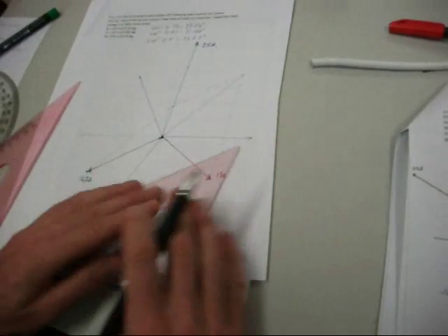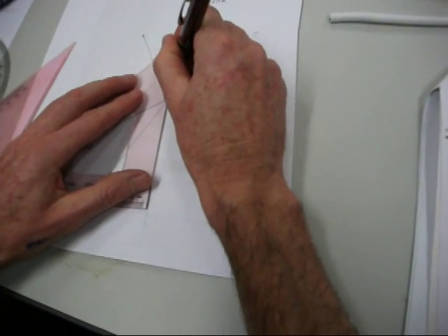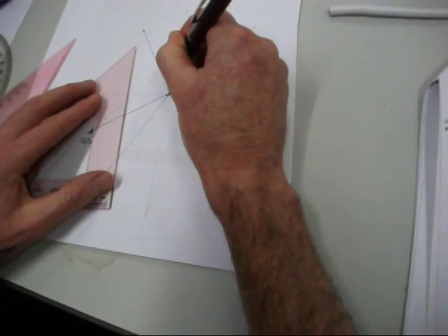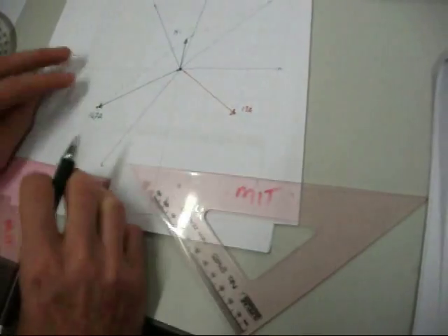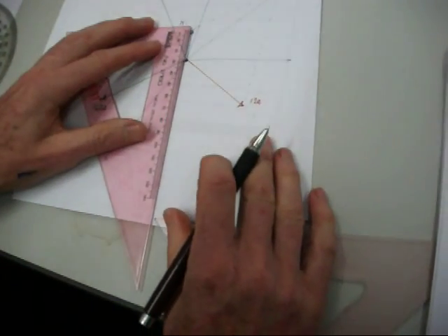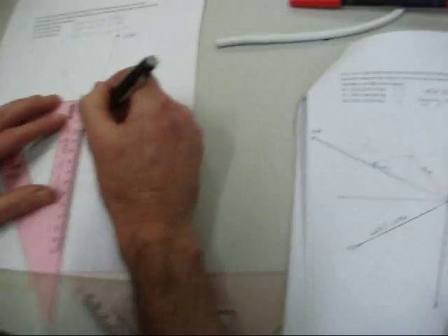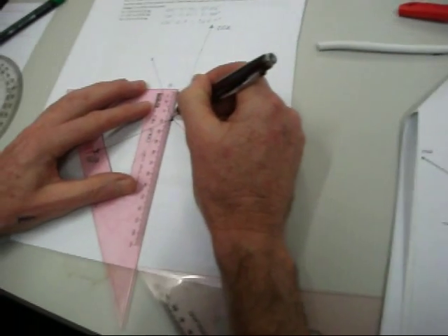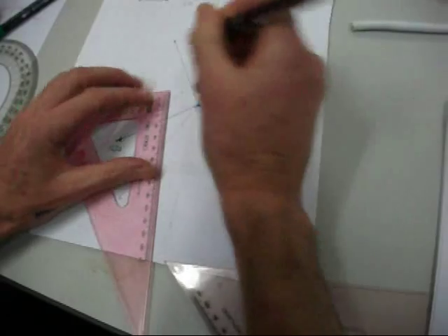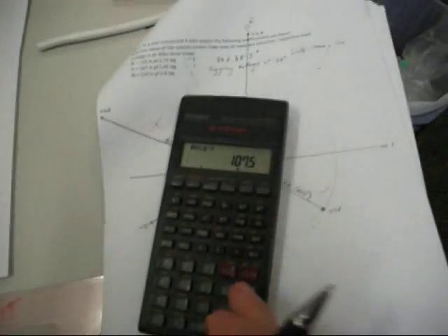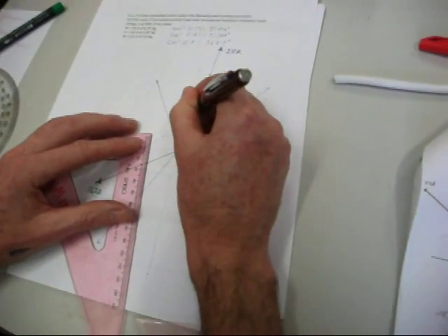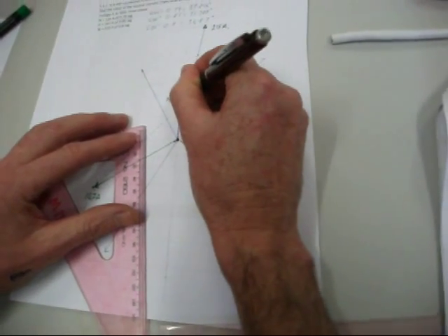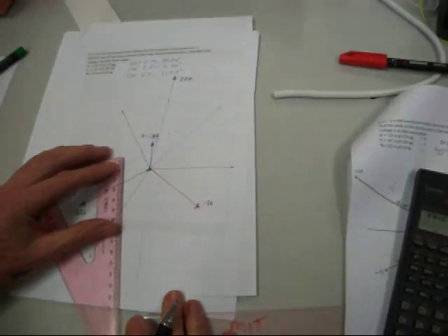Where the two meet is a neutral current. It measures 25, 26, 27, 28, 29. 29 times 2 because we're using a half scale, 58. So 58 amps neutral current, that's the answer.